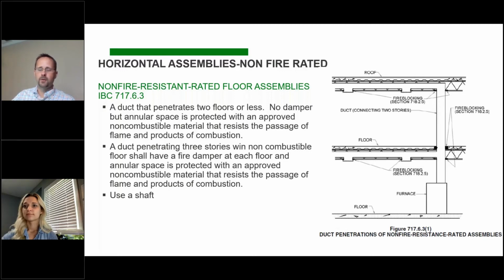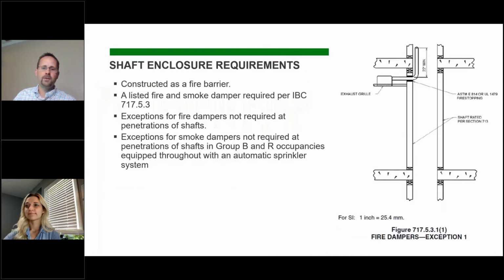And again, throwing fire dampers in is really easy to do on a plan, but in installation, fire dampers in floors are pretty tough. So really think that through and how that assembly is going to work before you jump to that option. And again, you can always have a fire rated shaft, and that will meet the intent of the code as well. So when you have a shaft, what does that do to your ductwork?